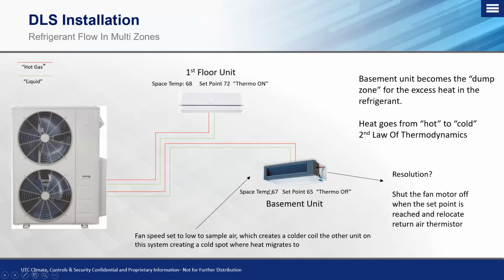So we're slightly overheating. So what we can do is we can go to our first floor unit and we can program this fan speed to shut off after set point. Once this fan speed shuts off after set point, that doesn't change the fact that hot gas is still going to flow to this indoor unit. So what happens is this creates a hotter coil temperature or surface coil temperature. While the basement unit, we leave that fan running. While that fan runs, that creates a colder coil temperature. Now, when I say colder, I don't mean 50 degrees, but it's much cooler than our first floor unit.